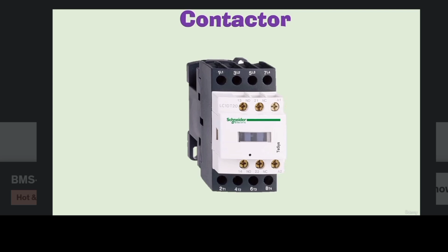Apart from the coil and switch contact points, contactors also have auxiliary switches which provide feedback about the latching status of the contactor. Here we have two auxiliary feedback contacts, NO and NC contacts, same as we saw earlier in the relays. When the contactor is energized, the NO auxiliary contact is latched and provides a feedback signal which can be connected to the DDC panel and can be monitored at the BMS workstation.